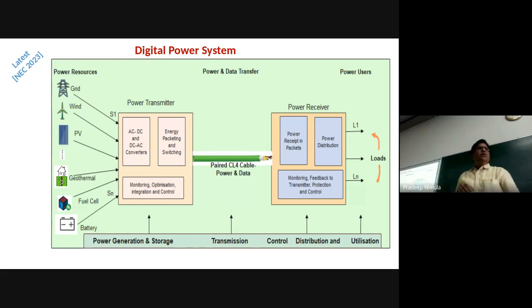The same cable will have 5 wires internally, 2 are for supply, phase and neutral. It will be insulated accordingly for 660 volt, insulation level will be high. The remaining 3 are used for control and other purposes, metering or whatever it may be. So what is the harm in this? The same wire is carrying 450 volt AC or DC. What is the harm?